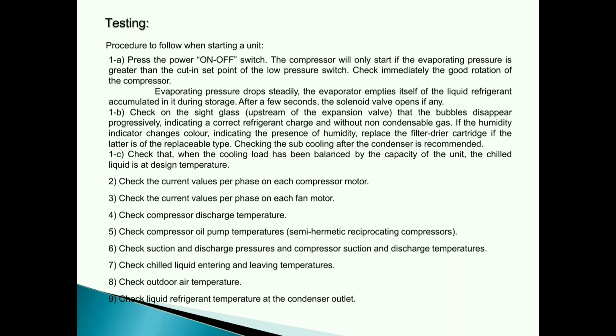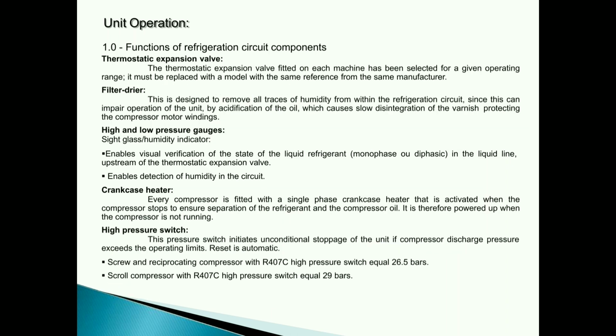2. Check the current values per phase on each compressor motor. 3. Check the current values per phase on each fan motor. 4. Check compressor discharge temperature. 5. Check compressor oil pump temperatures, semi-hermetic reciprocating compressors. 6. Check suction and discharge pressures and compressor suction and discharge temperatures. 7. Check chilled liquid entering and leaving temperatures. 8. Check outdoor air temperature. 9. Check liquid refrigerant temperature at the condenser outlet.